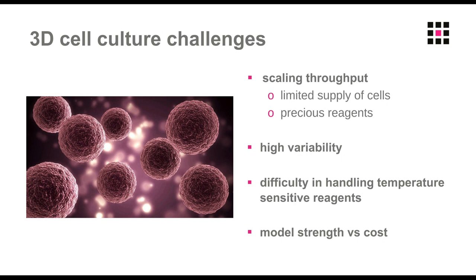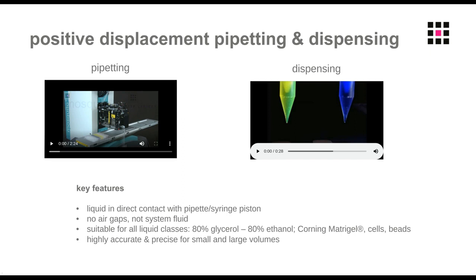At SPT LabTech, we use positive displacement pipetting and dispensing as the basis of our technology, either with low volume liquid handling — our Mosquito liquid handler setting down droplets transferring from one plate to another — or a dispense syringe. With positive displacement, the liquid is in direct contact with a piston that sits inside the pipette barrel or dispense syringe. It's really the direct movement of that piston on the liquid that moves it — there is no air cushion involved, no system fluid, no lines.